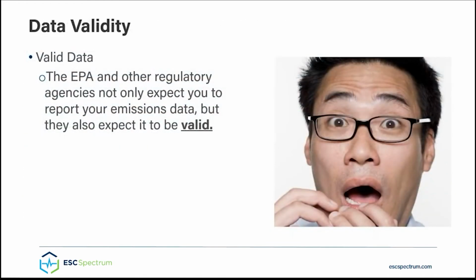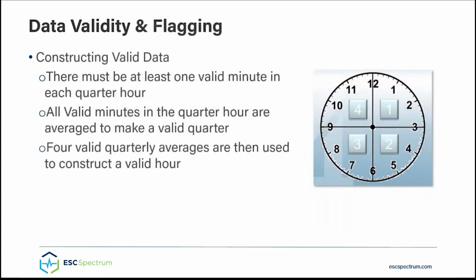Regulatory agencies only allow you to report data that is valid. So let's take a look at what that means and show an example from StackVision. One of the more common approaches for determining data validity requires you to record at least one valid minute of data in each quarter hour. All valid minutes in the quarter hour are then averaged to make a valid quarter, and four valid quarterly averages are then used to construct a valid hour.